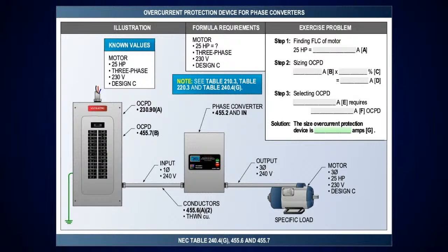Like this in here, this is simple. I just know what I'm looking at here. I know I've got to get the amperage, and I'm sizing an overcurrent device, so I know I have to use one of the tables. If I was doing overload, I know I need the nameplate. So I'll just get the amperage here. And based off what you just learned, we've got a fixed load here. It's a specific load, so I'm going to put 250% on here. And you just sort of learn the sections.